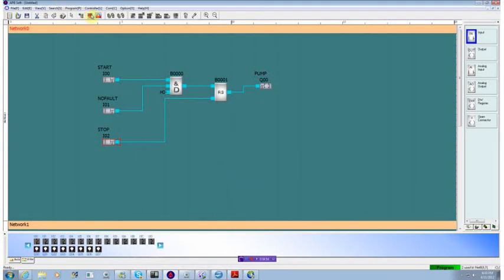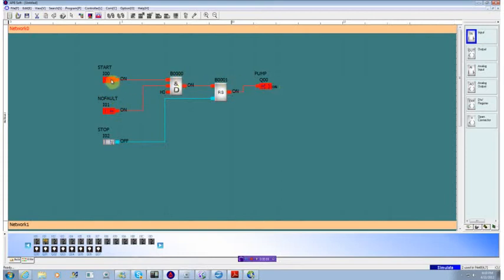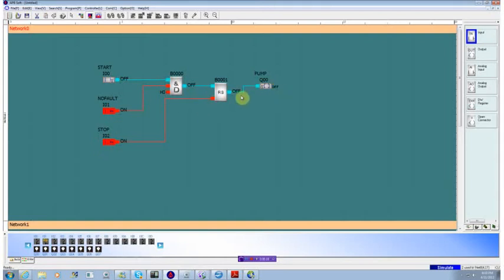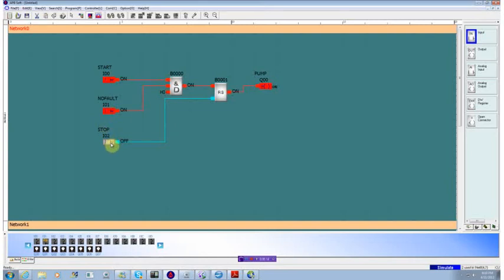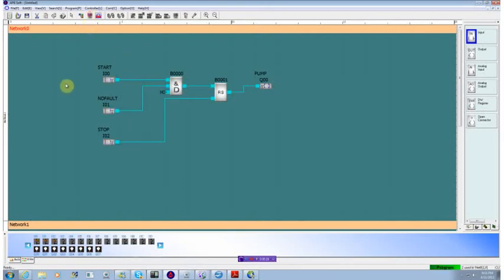Now when we hit our simulate button, we'll take it out of the fault condition. We'll hit start. We'll see how the pump immediately comes on. We'll turn off the start and hit the stop, and the pump immediately goes off. Now if we hit start and then hit stop, leaving it on, we see that the pump immediately went off because the reset will always take precedence over the set on the latch, which is exactly what we wanted it to do.